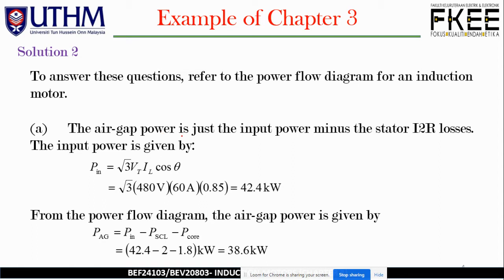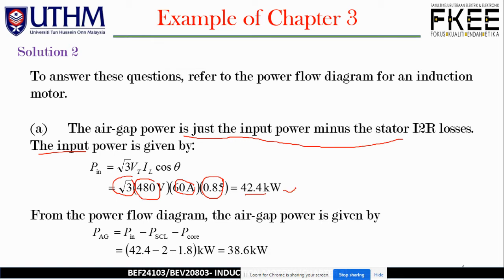Solution for Example 2, part (a): The air gap power equals input power minus stator copper losses. The input power is: P_in = √3 · V_T · I_L · cos θ = √3 × 480 × 60 × 0.85, giving P_in ≈ 42.4 kW. Then P_AG = P_in - P_SCL - P_core = 42.4 - 2 - 1.8 = 38.6 kW.